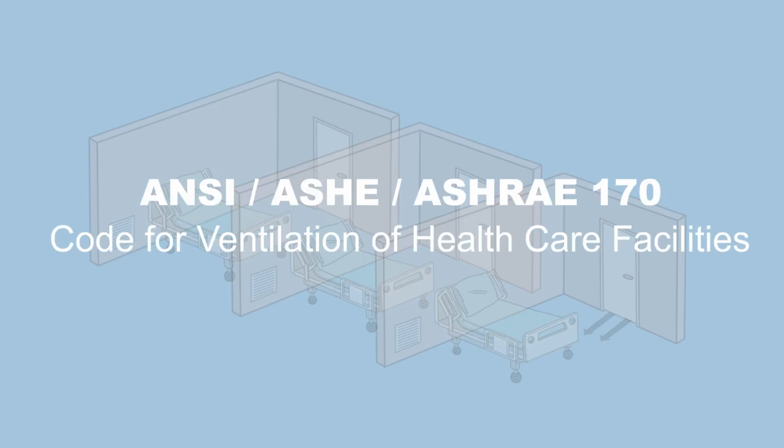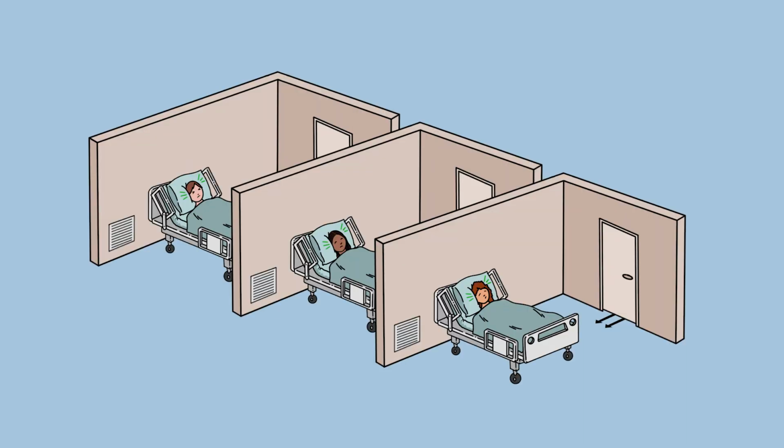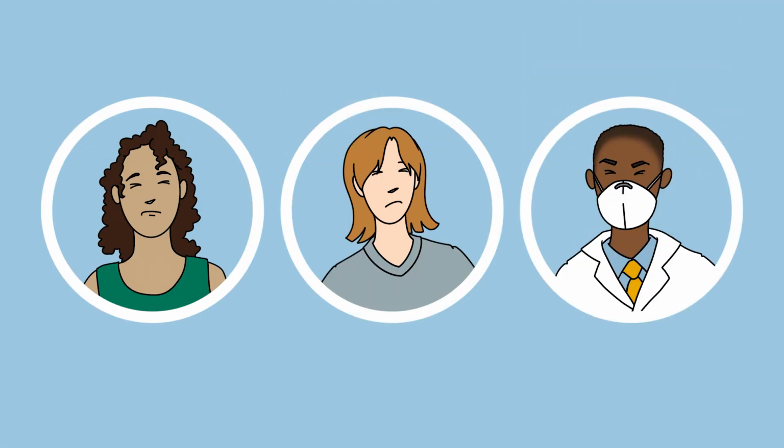This increase in return airflow can also overwhelm the discharge and return mixing box dampers, decreasing the total volume of outside air being brought into the building. ANSI ASHRAE Standard 170, which is the code for ventilation of healthcare facilities, bases the minimum total outside air requirement at the individual room level on the outside air changes per hour. A decrease in the code minimum required outside air volume will cause an increase in carbon dioxide levels. This may lead to occupant drowsiness and headaches, and even increase the likelihood of clinical mistakes, which can have life-altering effects in a hospital setting.